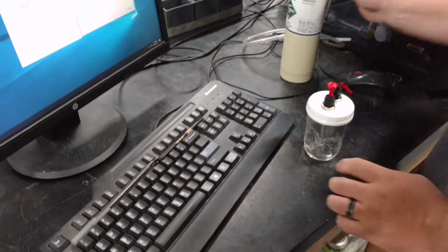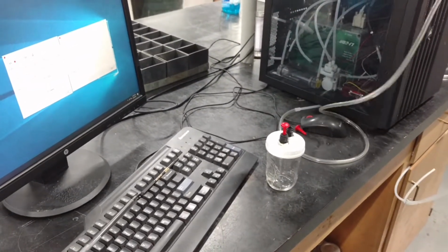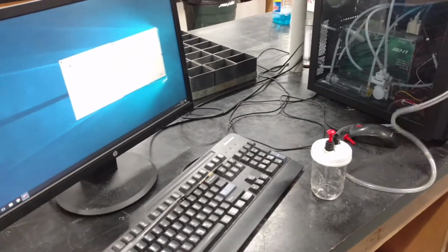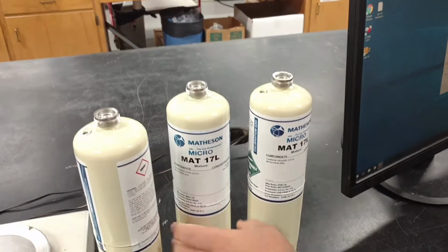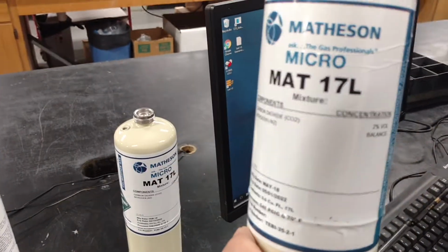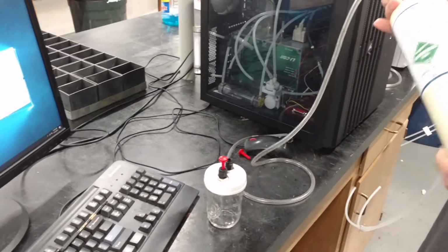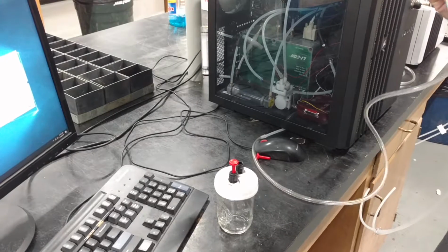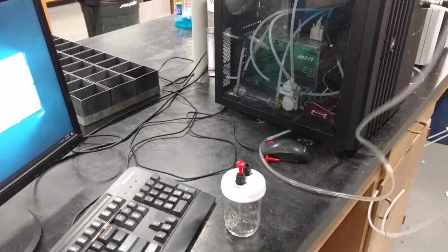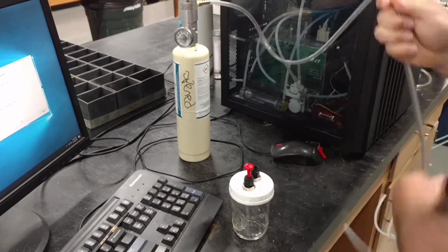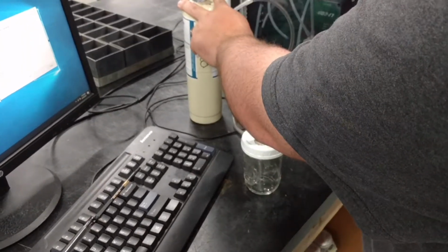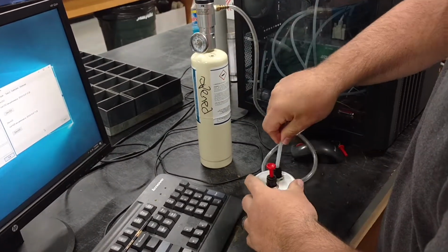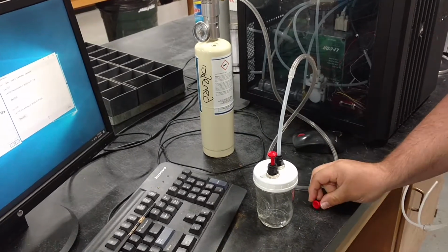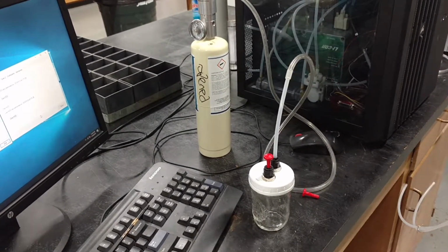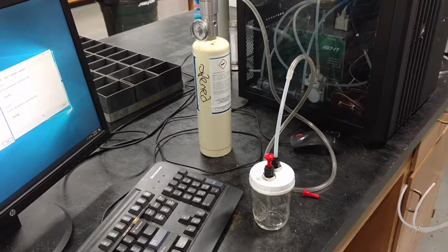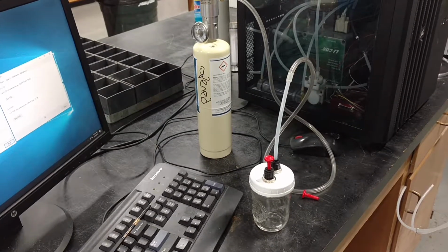With your first calibration point captured, you're going to disconnect the SR-1 from your jar and move on to the second point of your calibration. Disconnect your regulator from your canister and select your second canister. In this case today we're going to be using a 2% CO2 concentration. You can also use any other calibration gas that falls between the span that you're looking for. With the second canister attached, we're going to again set the regulator at about 2 liters per minute and connect that to your jar. Again, the red plug in the second port should not be pressed down. It should be loosely sitting within the second port to allow gas to escape from inside the jar.